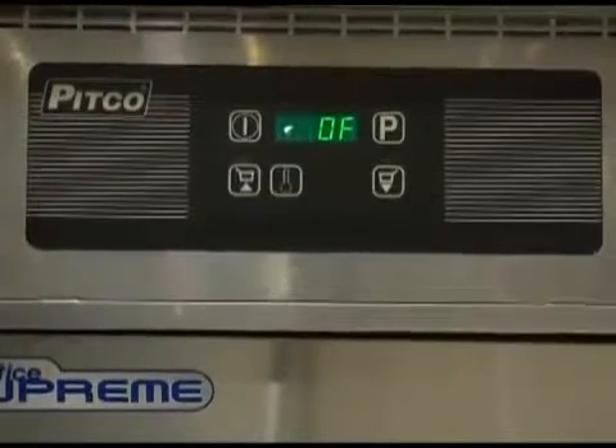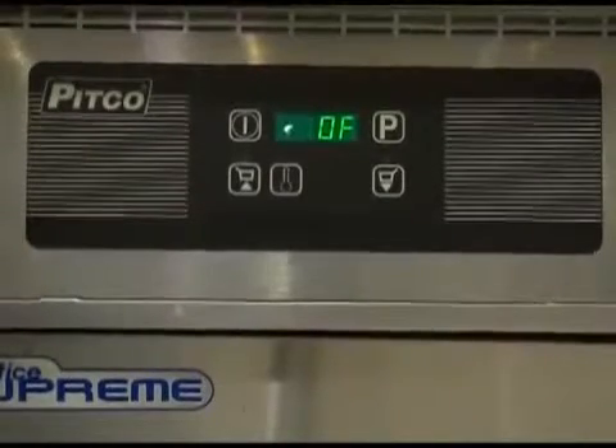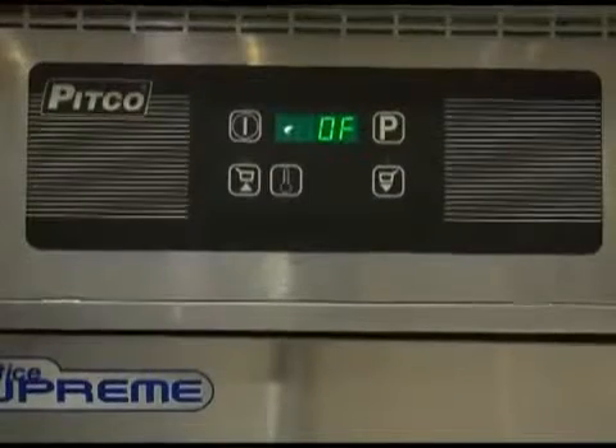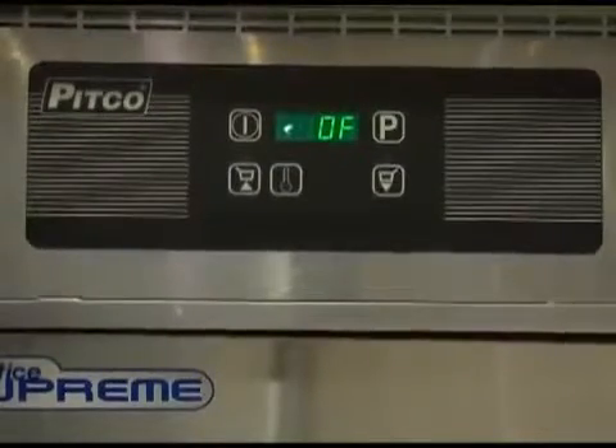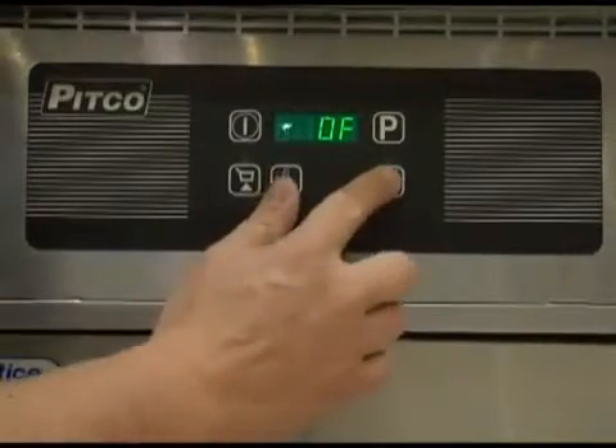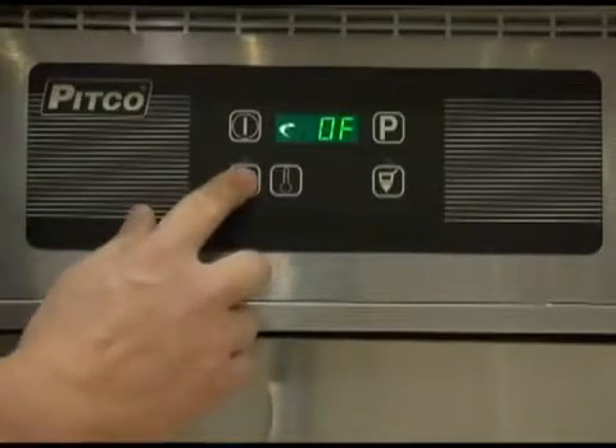This adjustment allows the control point to be adjusted to account for differences between probe tip temperatures and center of vat oil temperatures. The adjustment range is plus or minus 15 degrees Fahrenheit. Press the up and down keys to adjust.